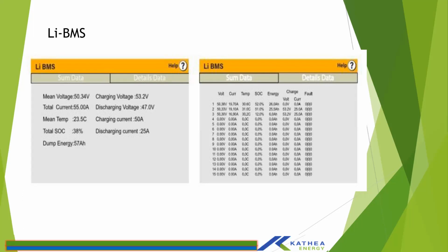So sometimes you find the battery has a fault, so it's not giving any output. However, the BMS would actually transfer data to the inverter to say the battery voltage is at this level and all that, but the physical output of the battery is not giving out that power. So you would need to measure your voltage at the termination and make sure that the voltage at the termination also tallies with Li-BMS when the inverter gives a low battery voltage fault.